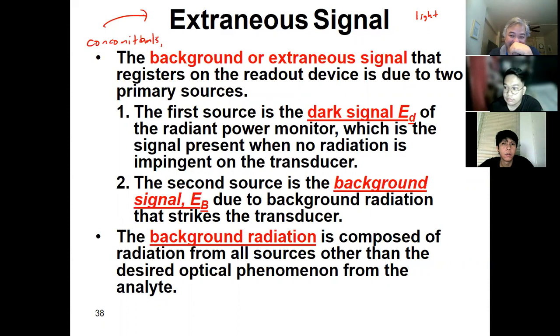That is how sensitive the detector is. We want the signal obtained by the detector to come from the sample that is being hit by our laser source. So when the light is opened, that can be lost. Or it will give another source of energy that can destroy the detector.